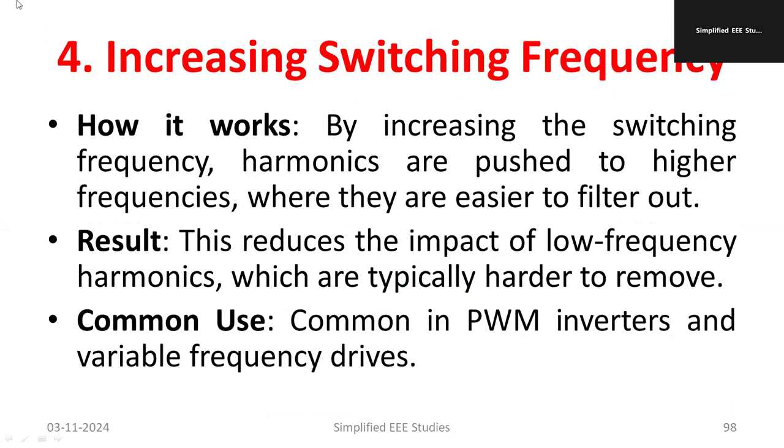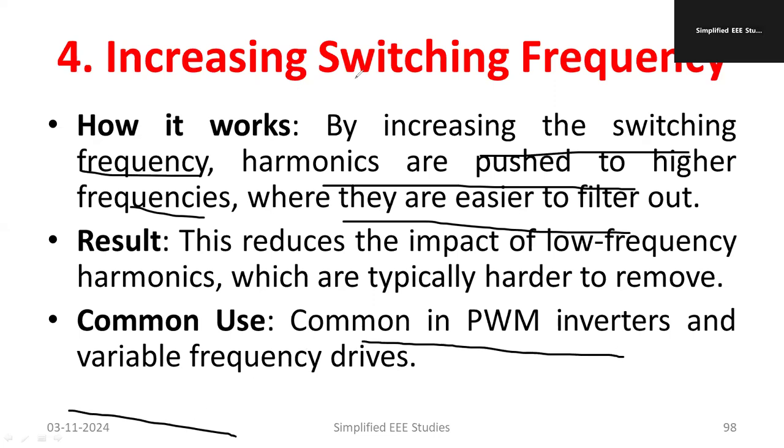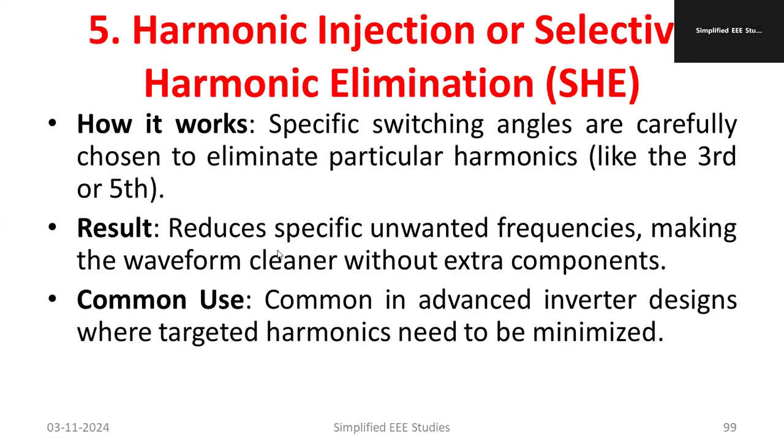Next is called increasing switching frequency. We need to select a high switching frequency devices such as IGBT or MOSFET. Here increasing the switching frequency harmonics are pushed to higher frequencies thereby easier to filter out. Lower order harmonics will be converted into higher value so that it is very easy to use the filter and mitigate it. It reduces the impact of low frequency harmonics which are harder to remove. That is another important thing. Common PWM inverters and VFD these are the major applications of increasing the switching frequency. Also the board size can be reduced if the switching frequency is very high. Losses will be minimized. So how many advantages are there?